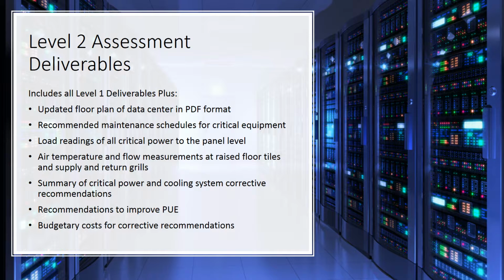Once the Level 2 assessment is complete, KNA will provide a full deliverable to the customer with all findings. This deliverable will include everything from the Level 1 assessment deliverable, plus an updated floor plan of the data center in a PDF format. This deliverable also includes load readings for all critical power to the panel level, along with the air temperature and flow measurements at the raised floor tiles and supply and return grills. A summary of critical power and cooling system corrective recommendations, along with any recommended maintenance schedules for critical equipment, will be provided. Any recommendations to improve the PUE will be provided as well, along with any budgetary costs for all corrective recommendations.